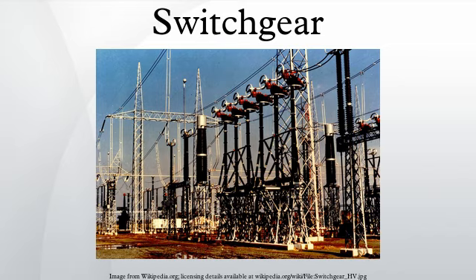Switchgear is often inspected using thermal imaging to assess the state of the system and predict failures before they occur. Other methods include partial discharge testing, using either fixed or portable testers, and acoustic emission testing using surface-mounted transducers or ultrasonic detectors used in outdoor switch yards. Temperature sensors fitted to cables to the switchgear can permanently monitor temperature build-up. SF6 equipment is invariably fitted with alarms and interlocks to warn of loss of pressure, and to prevent operation if the pressure falls too low.